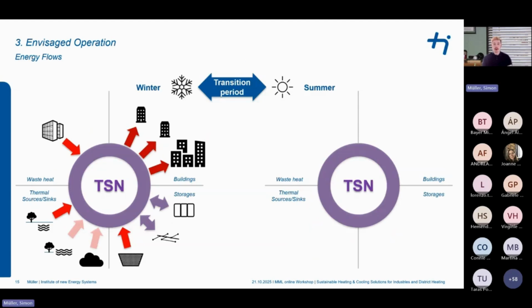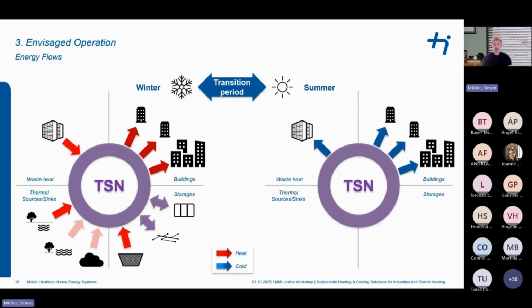Now, during summer, the demands of the buildings change, and most of them will have a cooling demand, or you could also say they supply exhaust heat to the network. The waste heat from the data center does not really help with that, but adds even more heat to the network. Accordingly, all the surplus heat is either charged into the S-TES, which is just another way of saying there is cold discharge from the S-TES.